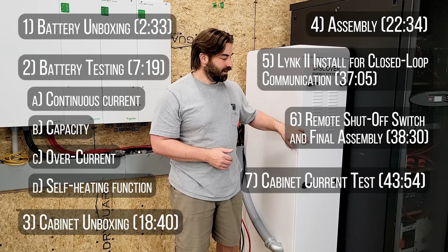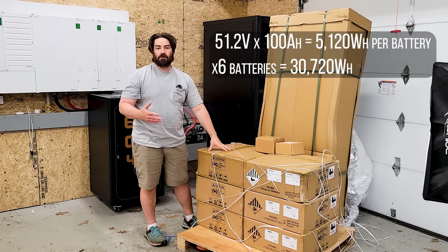Today we have a brand new option from Discover Battery. This is the cabinet and batteries here on the pallet. We're about to break into them and test them out. With the plastic off, we have a better view. The big tall box is going to be our server rack that's going to hold the batteries. Each battery is a 100 amp hour, 51.2 volt battery, lithium iron phosphate, a little over 30 kilowatt hours of storage. Then we have a Lynk II communication device, for closed loop communication with inverters. And this one isn't marked, but I think this is the large circuit breaker for overcurrent protection for the wires leaving the cabinet to go to the inverters.